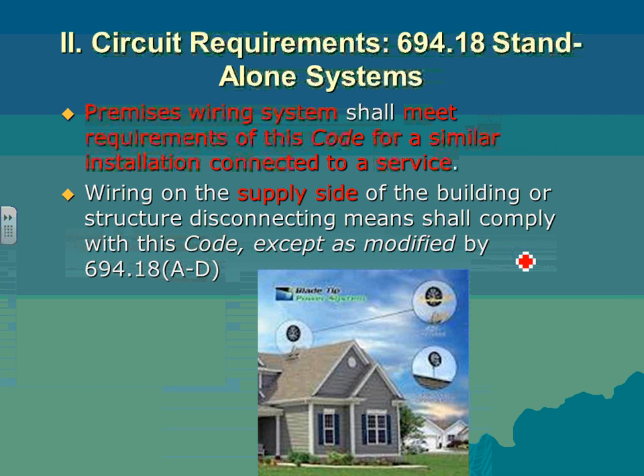And then moving on, that's basically for all the systems. Moving here, guys, is a standalone system. What happens if you have a standalone system? You don't have a grid. Then everything that we said so far, you have to apply the same rules. Wiring on the supply side of the building, there is no supply. You are living in the boonies and you have a standalone system.